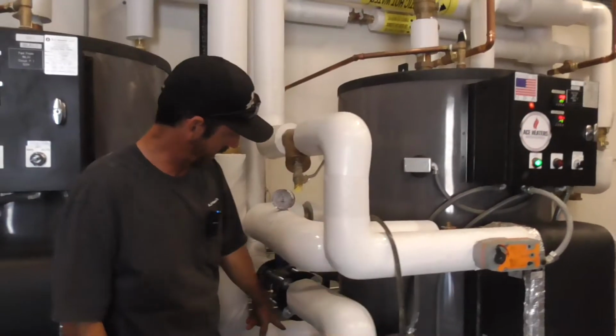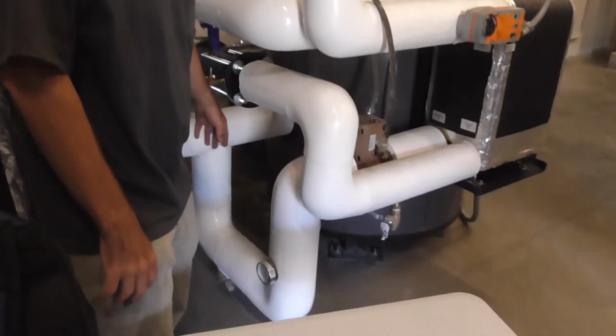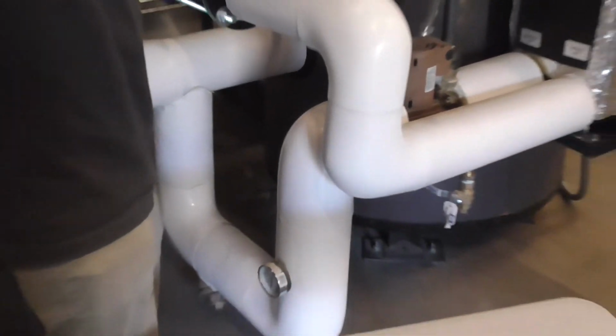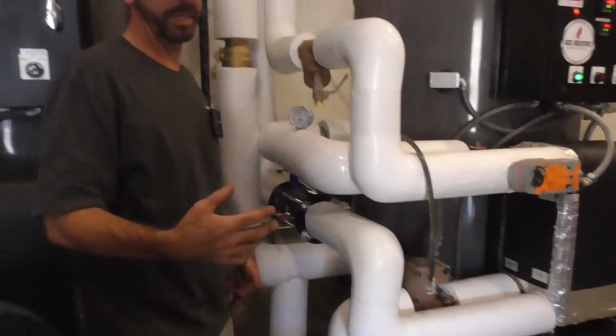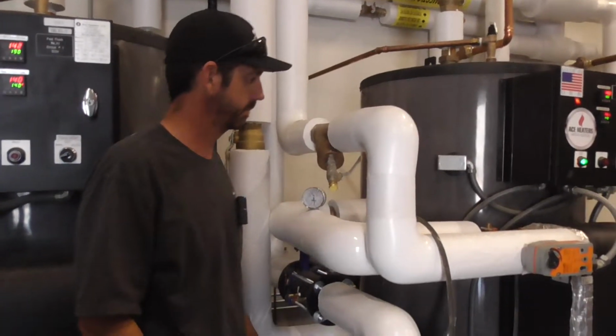There's drains down at the bottom of the tank. I'd recommend quarterly blowing those down at the bottom. I did miss drains at the bottom of our heating hot water pumps. There's drains at the bottom of the suction diffusers. Those would be good to blow down quarterly as well.